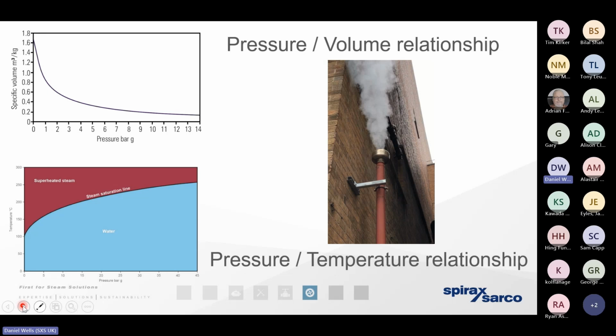We've got to vent that expansion away, but whilst those steam vents are left unchecked, it essentially means that the boiler's working harder and harder to replace that missing steam. So we've got more steam going into the sky, and of course, we now no longer have that opportunity to recover and return the condensate. So our cost of steam, cost of gas, and our carbon emissions are going to increase significantly. So even before we move to look at the areas for optimizing and improving efficiency, we really need to take note of the information that's staring us in the face. Those vents are telling us that there is a significant inherent inefficiency that needs to be addressed immediately.